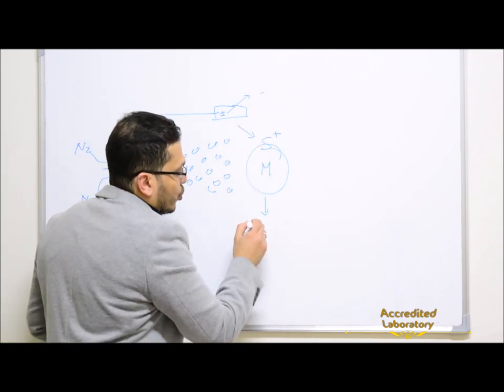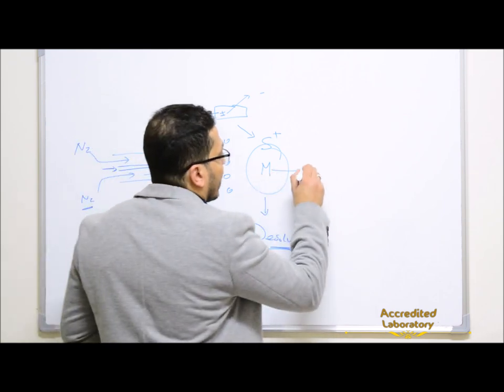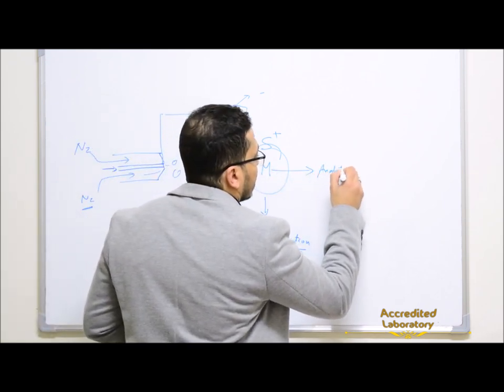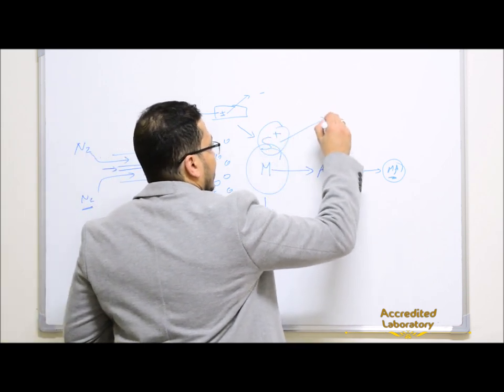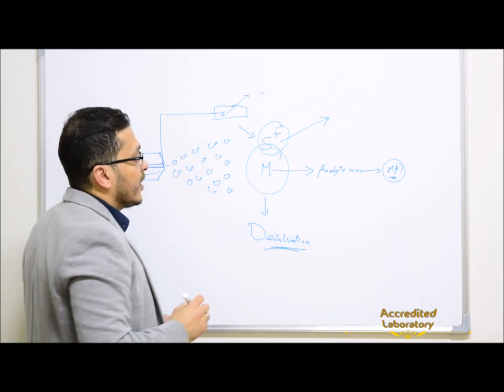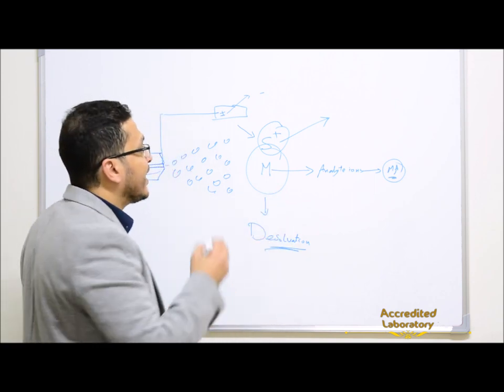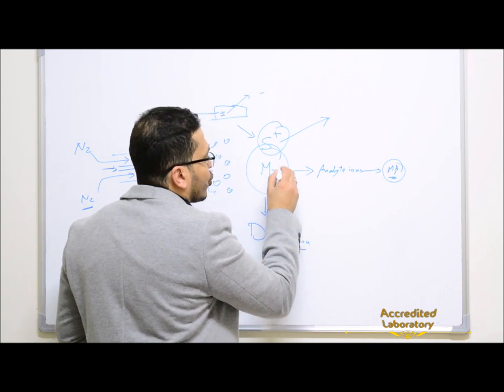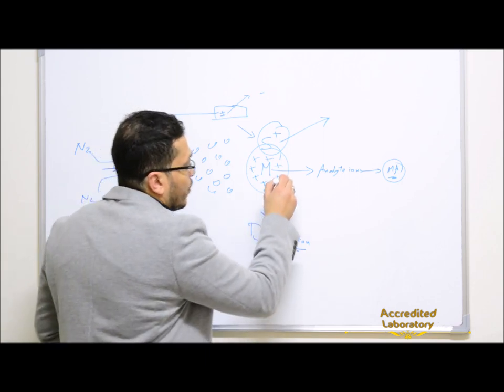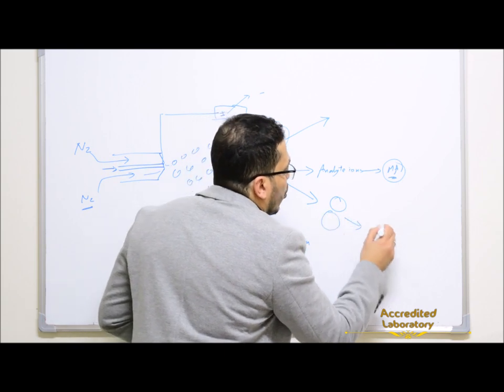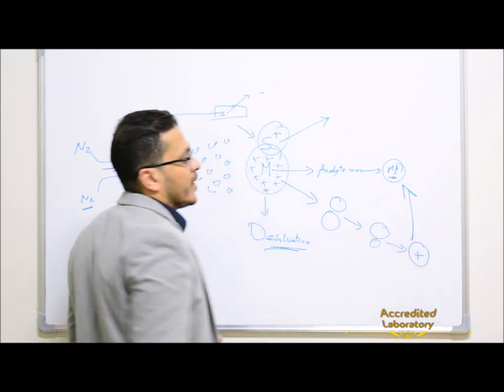After that, a desolvation process removes the solvent molecules, because only analyte ions should be transferred to the mass analyzer. These solvent molecules will be evaporated by the effect of temperature and drying gas, resulting in a decrease of the charged droplet radius and increase of charge density. Repulsion between the like charges becomes higher than the surface tension forces of the droplets, breaking the droplets into smaller droplets, resulting in ejection of ions.